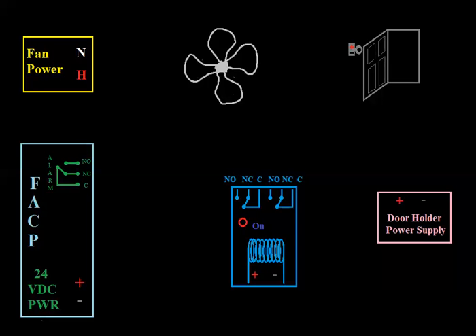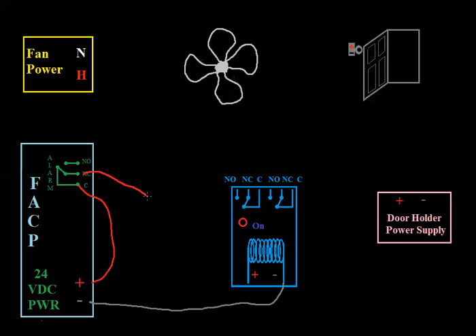To power this relay up, we're going to run the negative right to the negative side of the coil. We're going to run the positive through our alarm relay on the panel — this is just 24-volt power. I'm going through common and it comes out to normally closed. Once this thing gets power, assuming the panel is in a normal state, this relay comes on. There's a little light showing the relay is on, and these contacts change states.